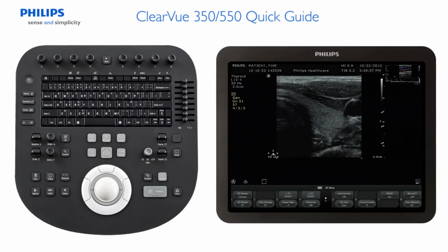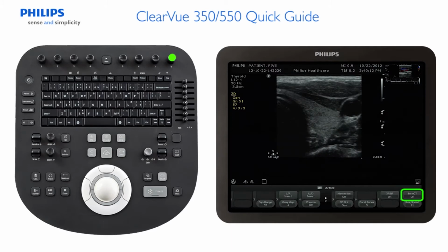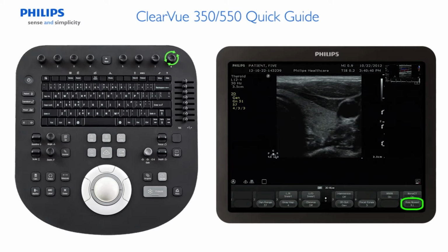Sono-CT real-time compound imaging uses spatial compound imaging to reduce speckle, enhance contrast resolution, and improve definition of tissue interfaces. Sono-CT can be activated by pressing the Sono-CT Quick key. Sono-CT has two modes, Res R1, which will give the user the best resolution with a slight decrease in frame rate, and Speed S1, which will give the user increased frame rate and a slight decrease in resolution. To switch between Res R1 and Speed S1 modes, turn the Res Speed Quick key.